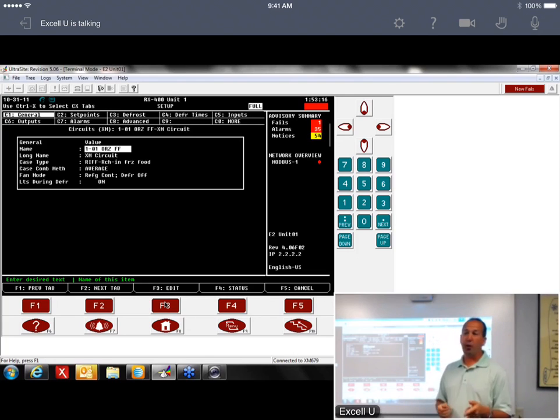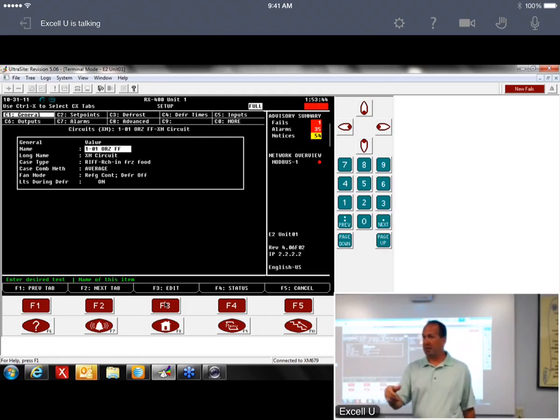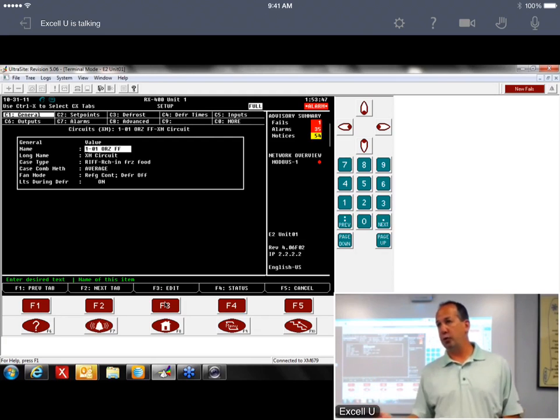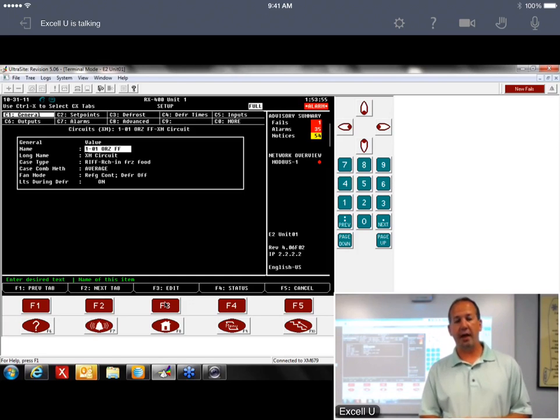And if you're upgrading firmware, let's say you have CCBs and you're on 2.7 firmware and you're adding some Dixells, so what? Manual change? No, what'll happen is when you upgrade, say you're at 2.7 and you upgrade to 3.06, it's going to change those names for you. Where you have duplicate names, the last couple of digits may get changed arbitrarily to 01 or 02 or something, but the firmware upgrade will change those names because, like I said, it no longer allows that to happen.